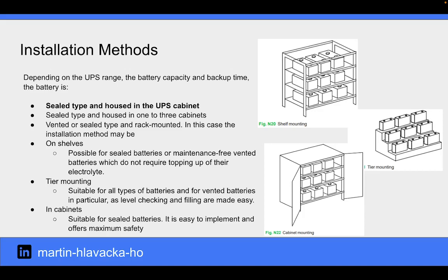Depending on the UPS range, the battery capacity and backup time, the batteries are sealed type and housed in the UPS cabinet, sealed type and housed in 1 to 3 cabinets, or vented or sealed type and rack mounted. In this case, the installation method may be on shelves. This installation method is possible for sealed batteries or maintenance-free vented batteries that do not require the topping up of the electrolyte. Tier mounting. This installation method is suitable for all types of batteries and for vented batteries in particular, as level checking and filling are made easy. Or in cabinets, this installation method is suitable for sealed batteries. It is easy to implement and offers maximum safety.